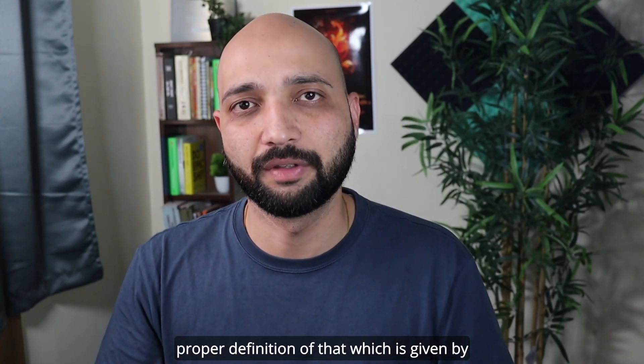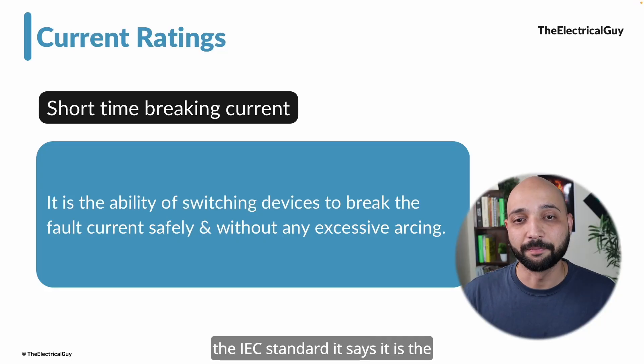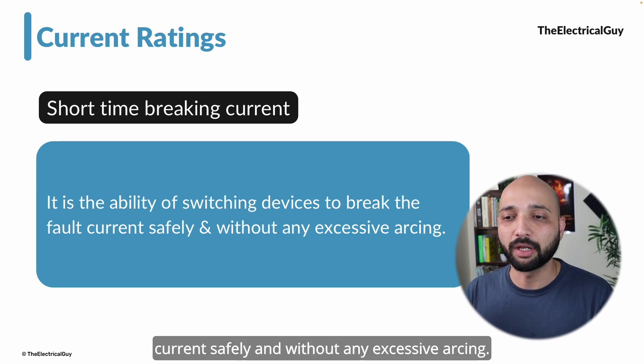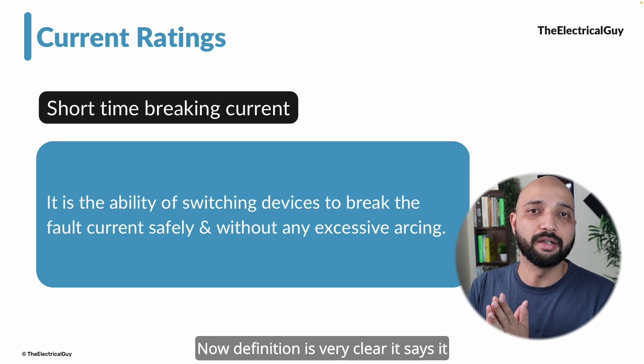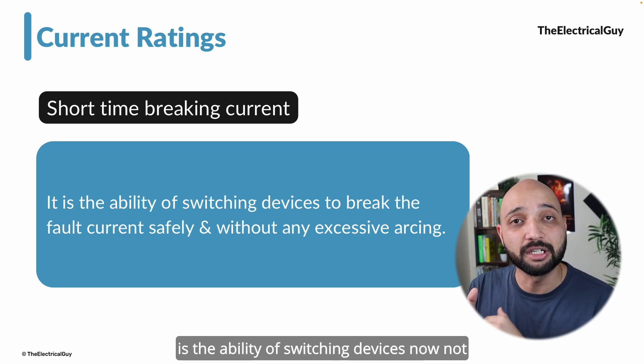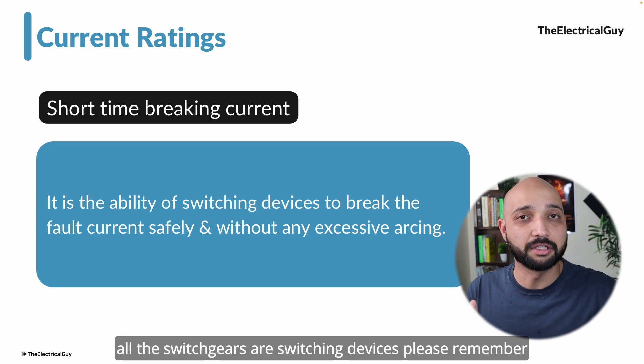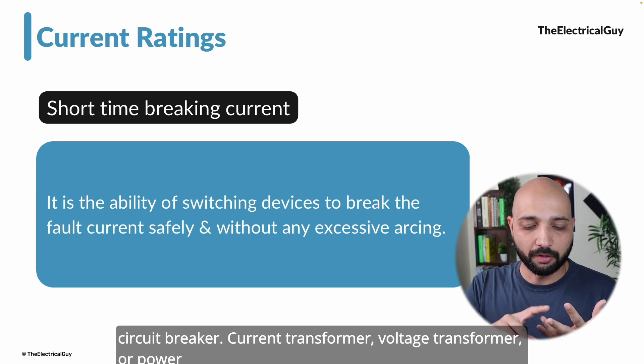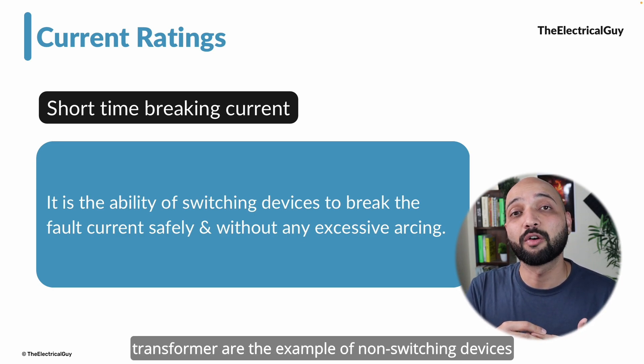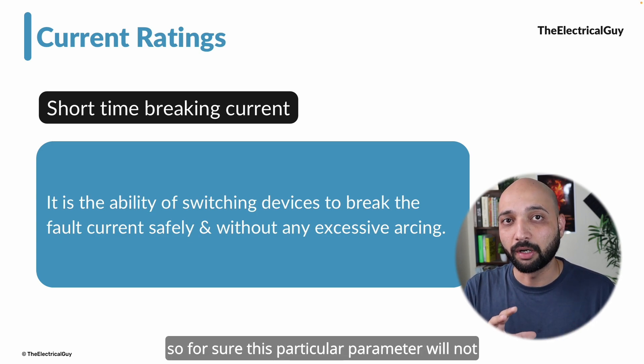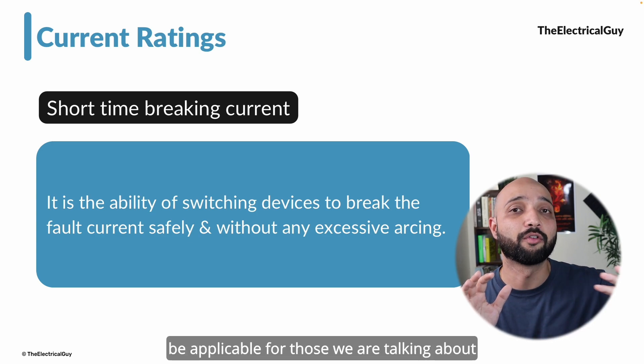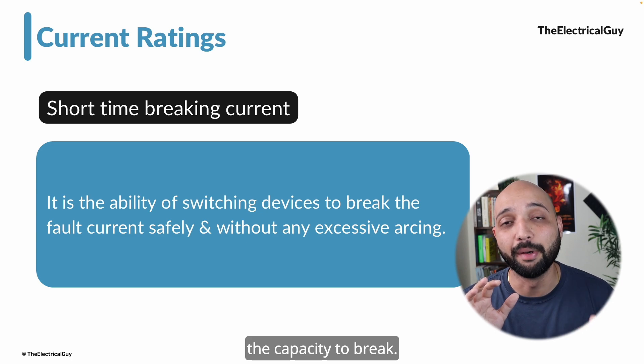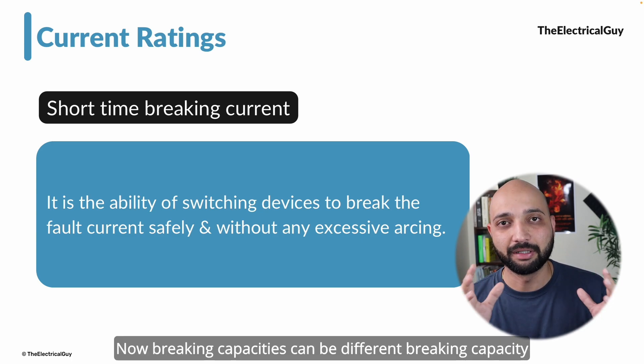Looking at the proper IEC standard definition: it says it is the ability of switching devices to break the fault current safely and without any excessive arcing. The definition is very clear — it says switching devices. Not all switchgear are switching devices. A circuit breaker is an example of a switching device, while a current transformer, voltage transformer, or power transformer are examples of non-switching devices. So this parameter will not be applicable for those.